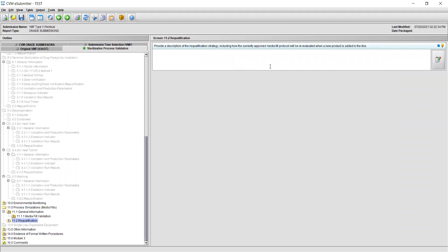On this screen, provide a description of the requalification strategy including how the currently approved media fill protocol will be re-evaluated when a new product is added to the line. This should include what containers and closures are used for requalification studies and which containers and closures are covered by the bracket but are not requalified. If a matrix, split fill, or rotational approach is utilized, justification should also be provided here. Please save your responses. You have now successfully completed section 11.0 Process Simulations Media Fills.